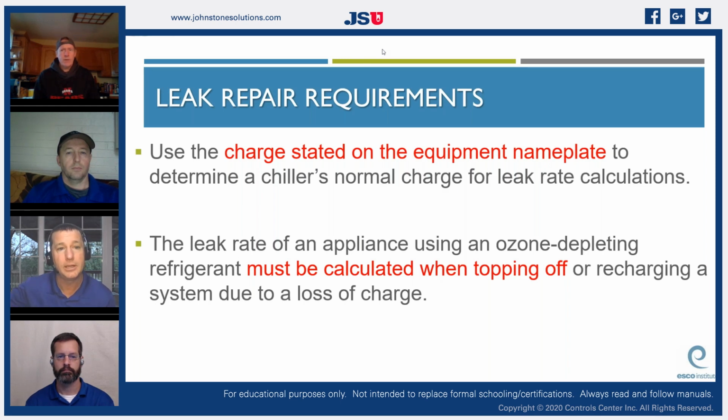You know, if I'm talking about a commercial VRV system, that's probably going to have 50 pounds of refrigerant or more in that system. I may have to go back to the original engineering data to find out what the original refrigerant charge was for that system. Because what if I put 31 pounds in it and I go, oh, okay, I hit my leak rate threshold, but because my nameplate says that my outdoor unit had 100 pounds, and then I go look at my system and I find out, oh, well, I may actually have 140 pounds in this total system, which has changed your leak rate threshold.